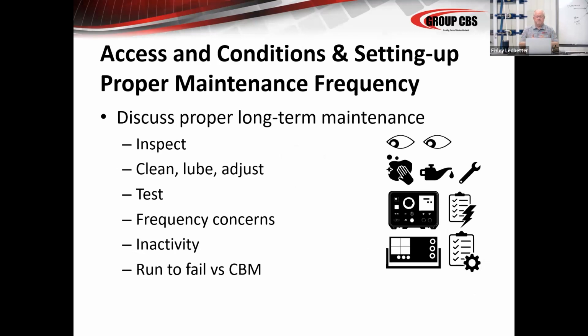Proper frequency is something we can talk about for hours. Basically, we've kind of proven that after 5 years, the lubrication begins to fall off and the times and speeds and velocities of the breakers begin to slow down. So I think it's generally accepted today that it should be less than 5 years in between maintenance cycles. If I had to pick a time, I would say the sweet spot's probably about 3, but that depends upon the atmosphere, the condition, the dirt, the type of equipment, who made it.